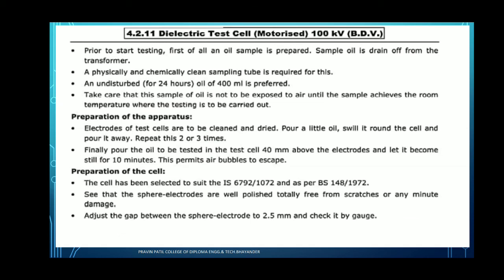We will test in our lab. So a dielectric test kit is available in our lab. We will take the procedure as well as the readings of the dielectric test. Near about 30 kV per mm dielectric strength is required for natural dielectric testing. So we will test the dielectric strength of the transformer oil in our lab.